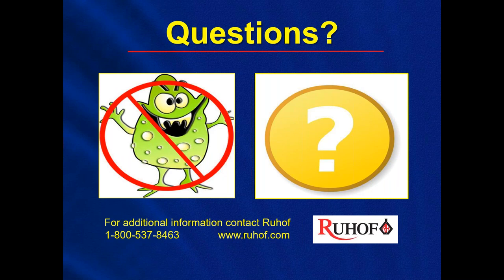So there's your answer right there: the ATP test is a test for your cleaning process, not your sterilization or high-level disinfection. So you do your bedside cleaning, your point of use cleaning, you do your manual cleaning, your drying, and you can test it at that point to see if you did a good job. If you did a good job, send it for high-level disinfection. If it didn't come back good, you're going to want to manually clean that scope entirely again and test it again before sending it out for your sterilization and high-level disinfection.